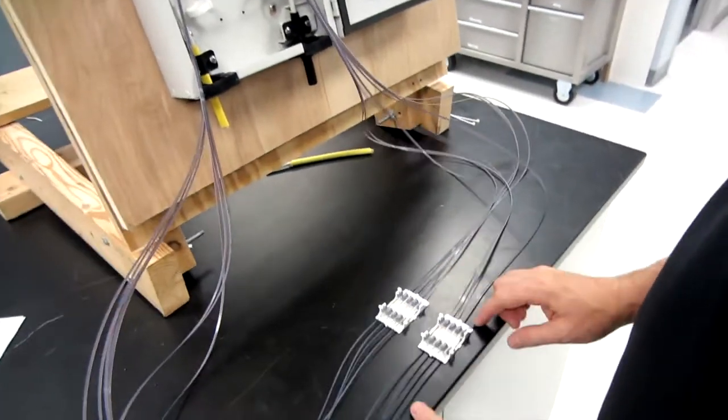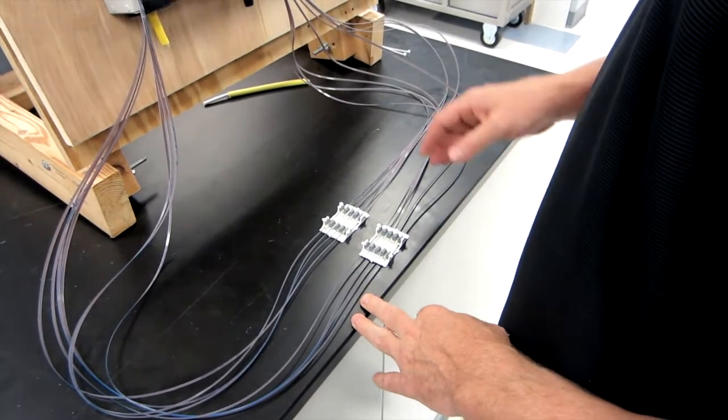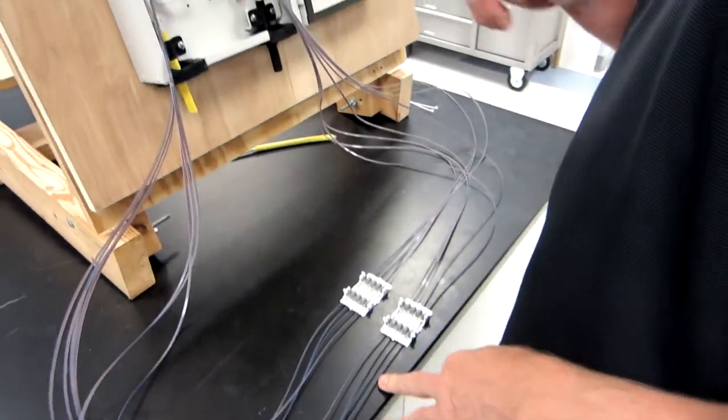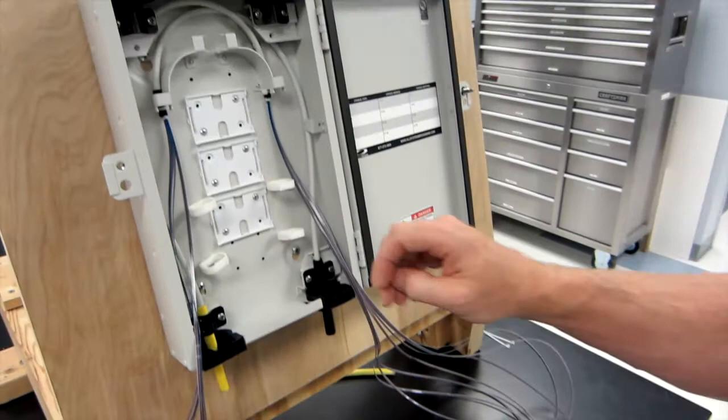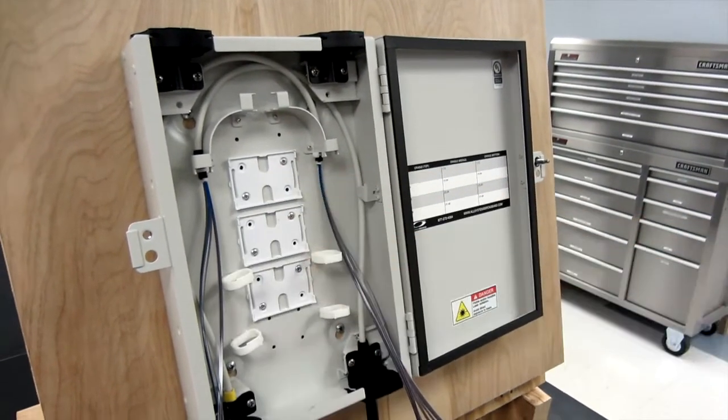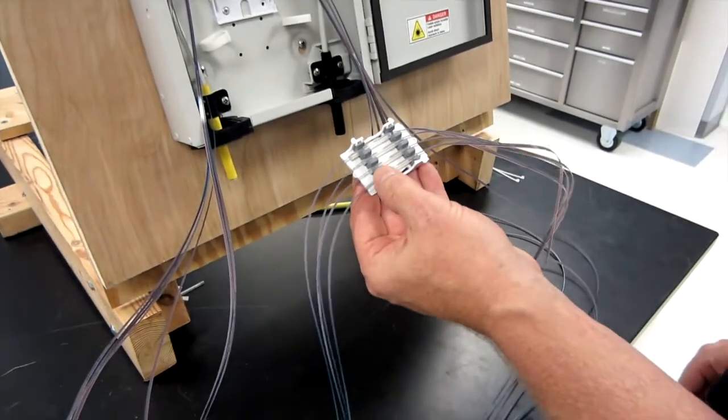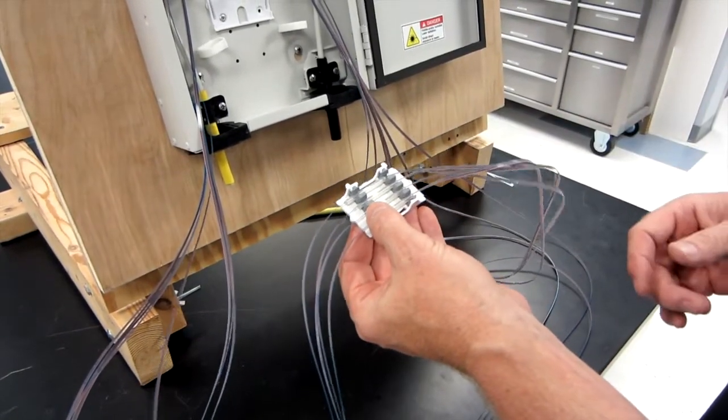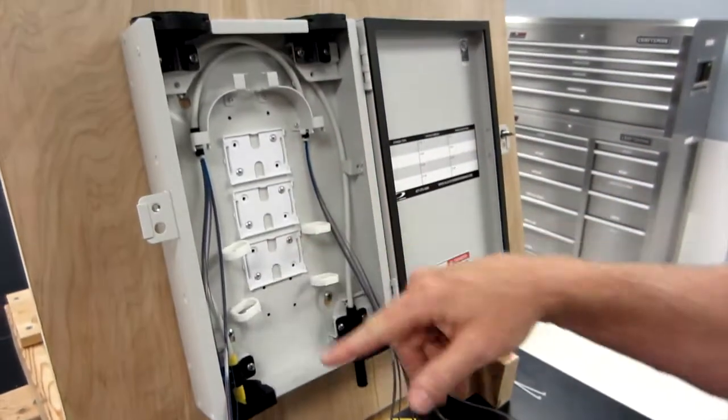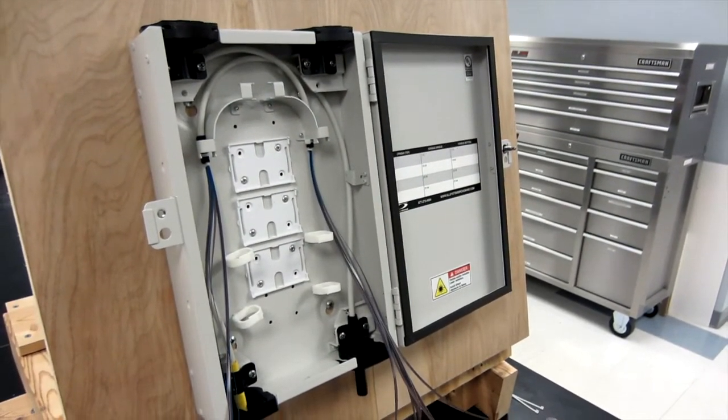All the twists have been taken out and our splices have been made. You can see in this small FSB box we have three cradle adapters. Each cradle holds four ribbons, so that's 48 count. 48 times 3 gives us 144 count capacity for ribbon in this box.